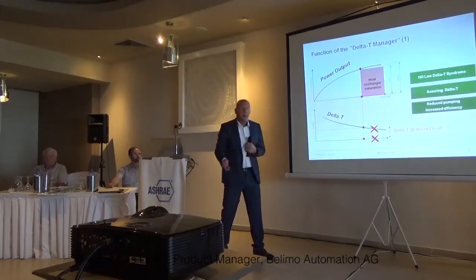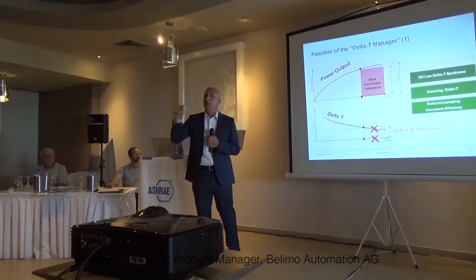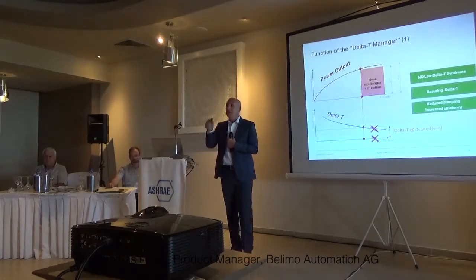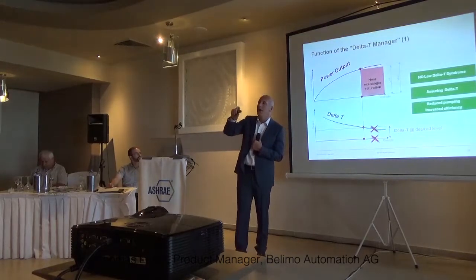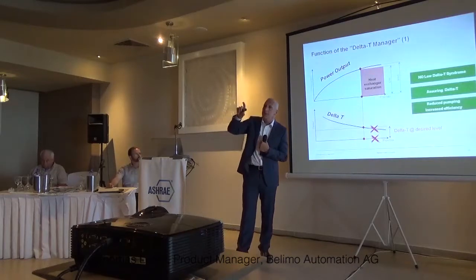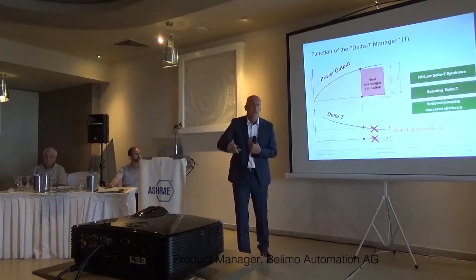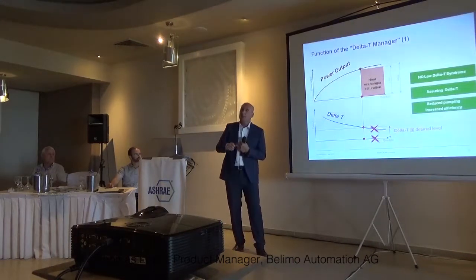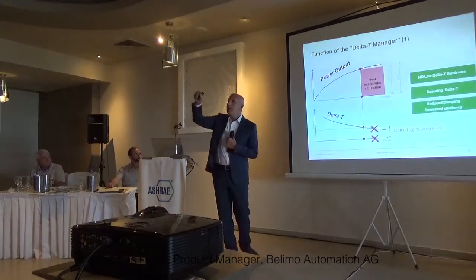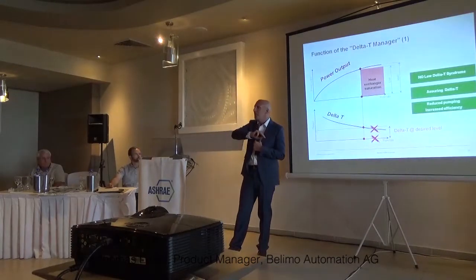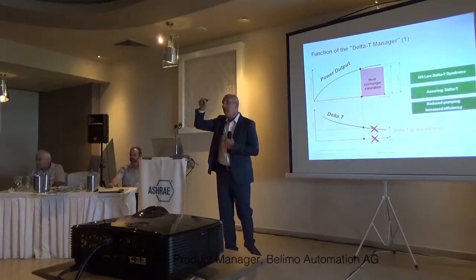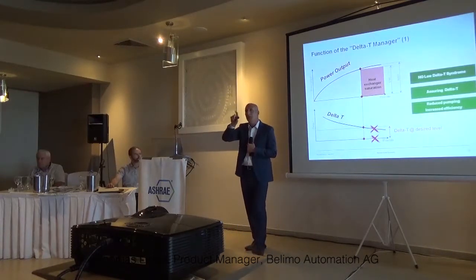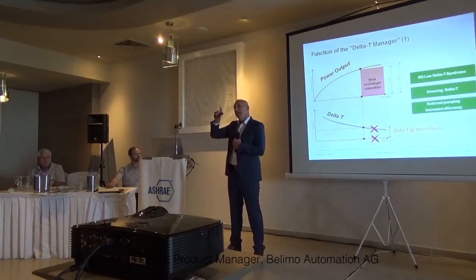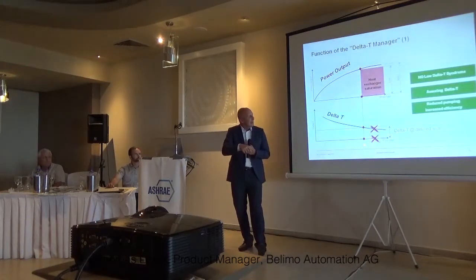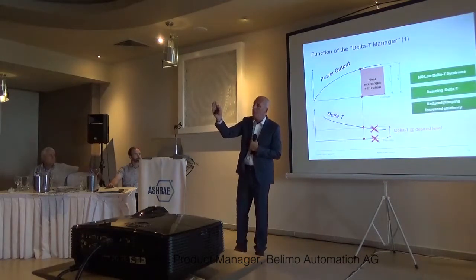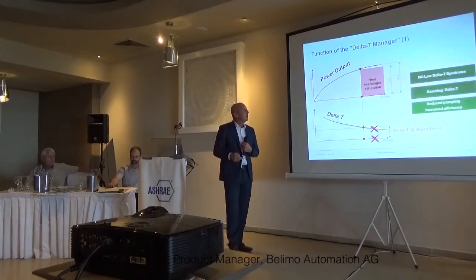at the saturation level. With a smart valve, you will be able to set this. You can tell a valve not to allow a water flow when the differential temperature between supply and return of my coil is below a certain delta T. Let's say 10 Kelvin. Even if there's a signal from the BMS to open the valve fully, the valve will react at the moment it discovers that the delta T is below 10 degrees. Then it will stop the valve opening, and it will even force the valve to close a little bit.